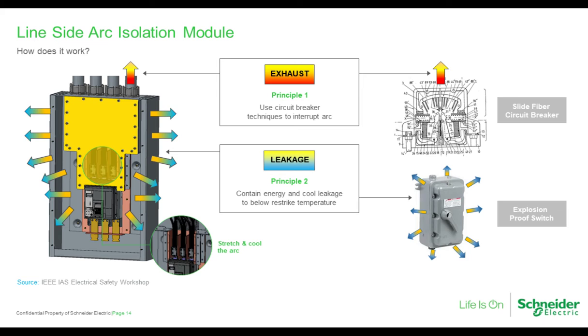And as much as we don't want the arc to get out, we also don't want one to get in either. Not allowing an arc to get in ensures that the load side arc cannot transfer to the line side, and it addresses directly the question of separation of zone 1 and zone 2. And in many cases, like in this example, that would mean a 10 times increase in incident energy. With ArcBlok, the overlap seals make the chance that a viable arc could enter the module very, very small.